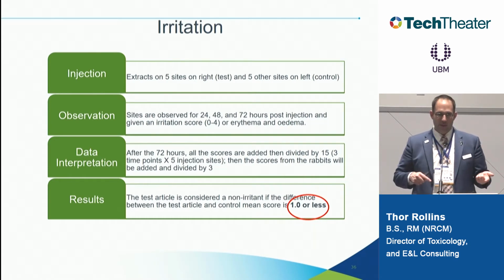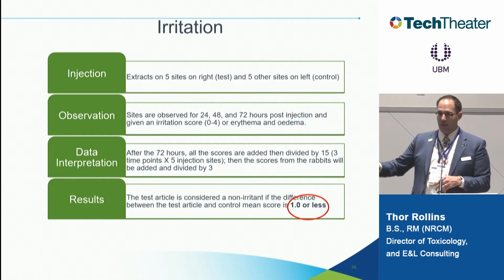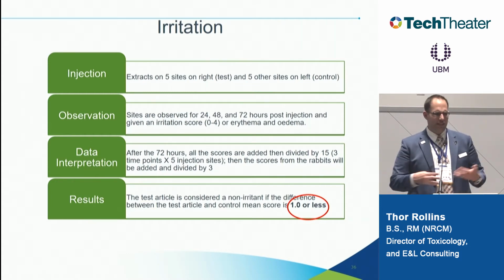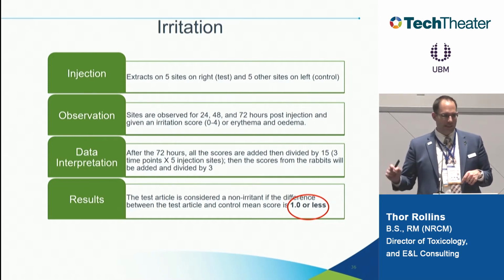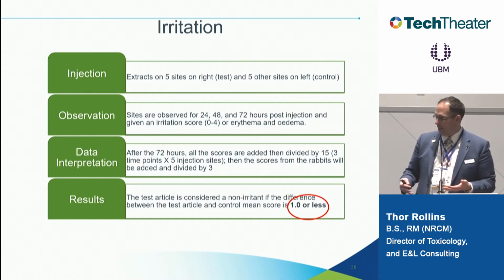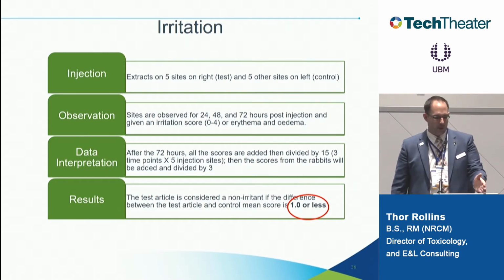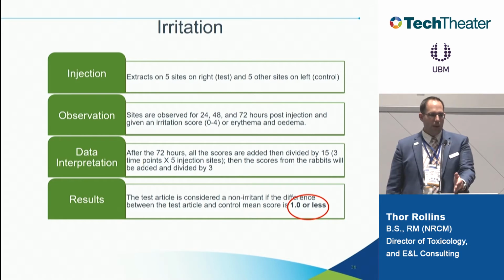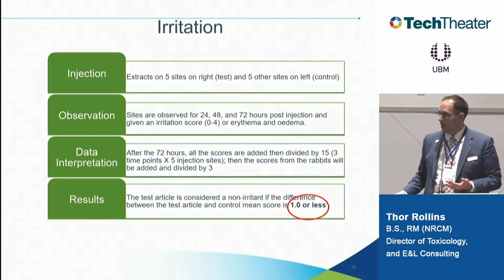Not the same irritation response that my wife gave me when she got home, but it's still an irritation response. So this one has to do with all of us. All of us have had irritation responses, right? So this is an immediate reaction to a stimuli. And we do this one in rabbits, and we observe them after we expose the device to the rabbits. We just look for 24, 48, and 72 hours, and we look for that redness and swelling. So that's an irritation test.